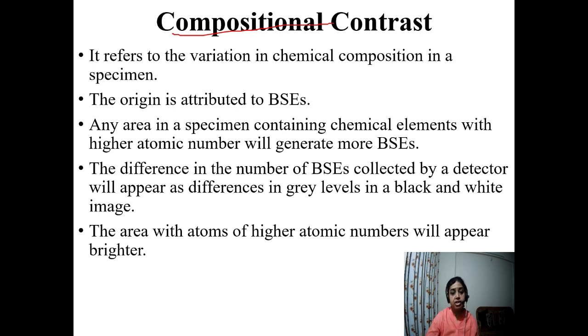As I mentioned at the very first, backscattered electrons are electrons which are scattered from atoms inside the sample. Suppose we have two materials, one is copper, the second one is tungsten. Tungsten has a high number of electrons, so scattering of electrons from tungsten will be higher than from copper. So the area where tungsten is present will look brighter than the copper. Due to that difference in the Z value, that is the atomic number, it will be seen in the image also. So basically compositional contrast is attributed to the backscattered electrons.